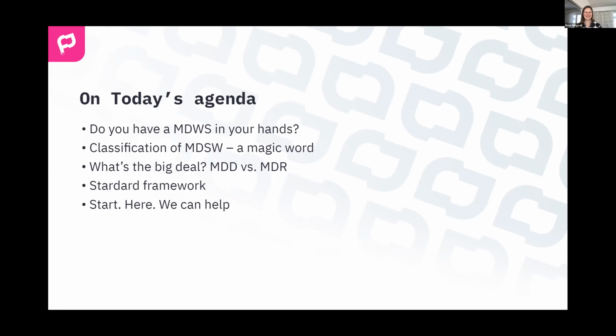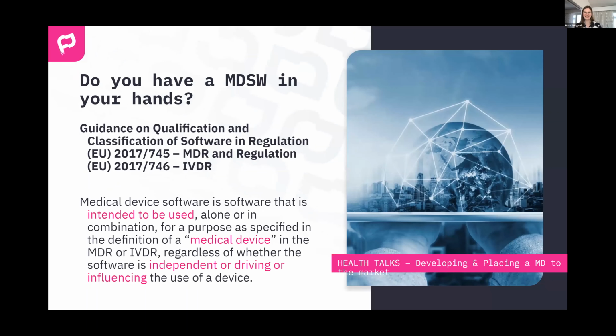So on the next slide, about the guidance of qualification and classification of software under MDR. Like Tuukka mentioned many times, it's about the intended purpose, intended use. So medical device software is software that has an intended use as a medical device. It doesn't matter if it's working independently or driving or influencing, for example, a hardware medical device, but if the intention is somewhat related to the medical device definition, then you have medical device software in your hands.